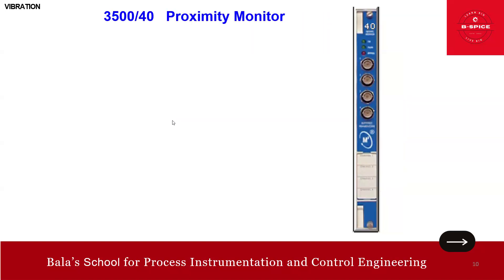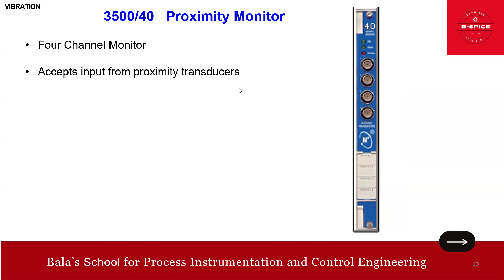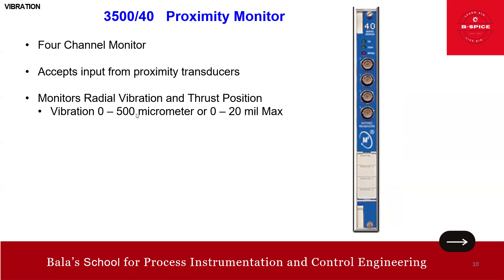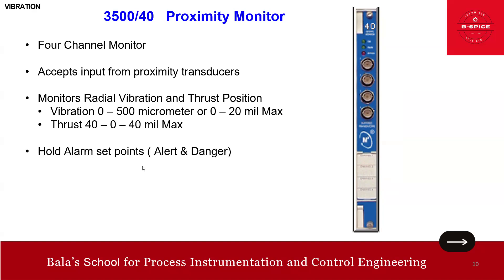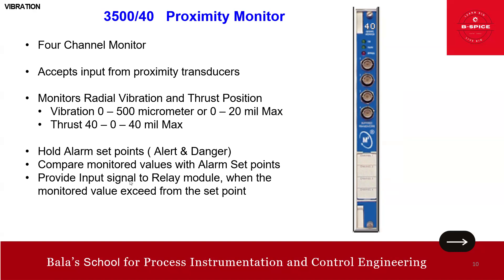Module 40 is the proximity monitor — again a four-channel monitor. It accepts inputs from proximity transducers and monitors radial vibration and thrust position. Radial vibration range is 0–500 micrometers (0–20 mil max), and thrust range is 0–40 mil max. It holds alert and danger alarm setpoints, compares monitored values against them, and sends input signals to the relay module when the monitored value exceeds the setpoint.